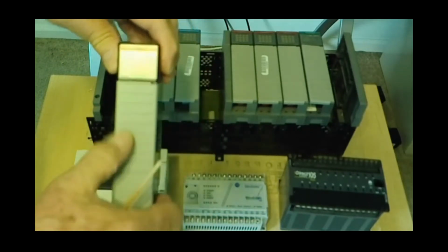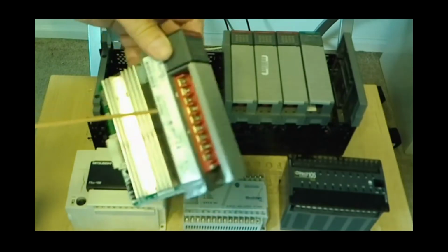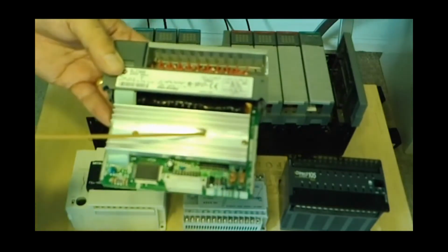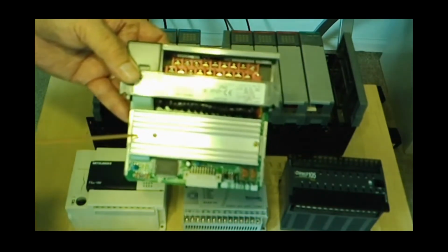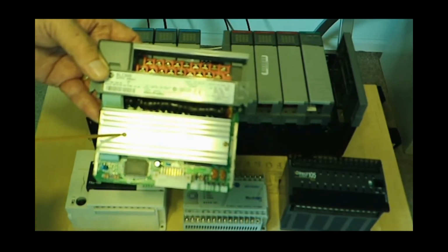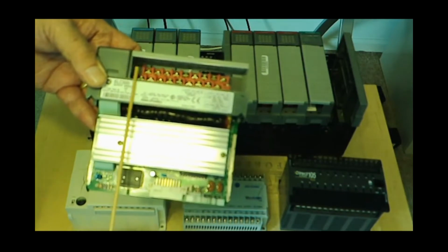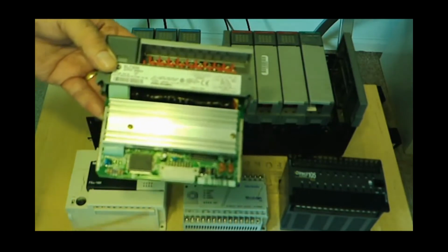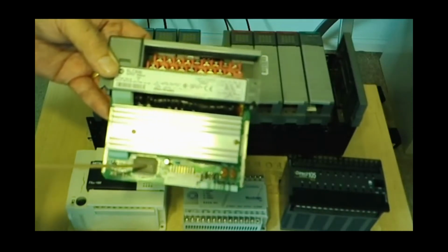This specific card is identified right here on the top as a TRIAC card. This entire unit underneath this heat sink is one long IC circuit with 16 TRIACs on that one circuit board. So it's not complex, there's just a lot of different circuits, one circuit for every terminal. And again, an individual CPU on the actual cards.